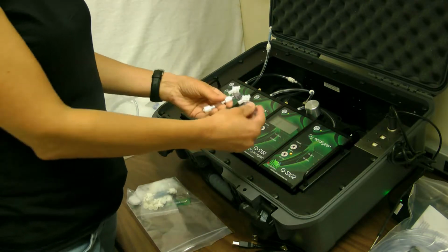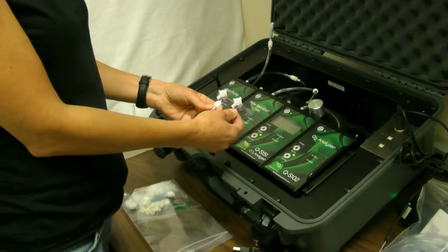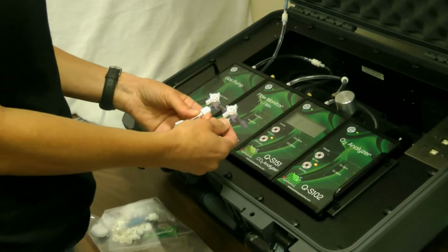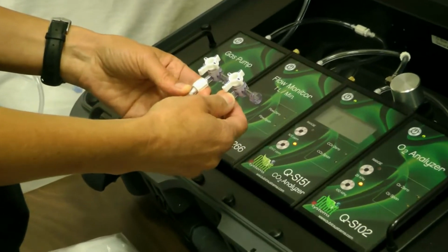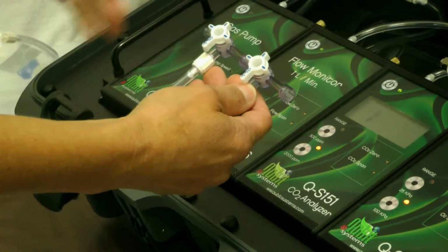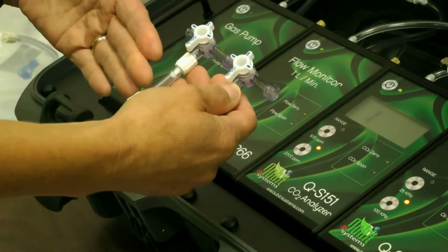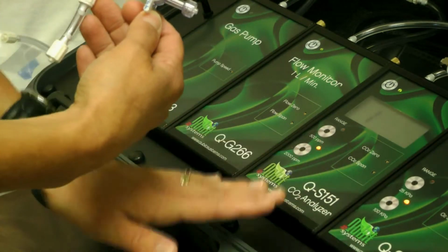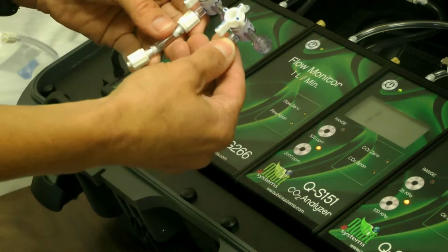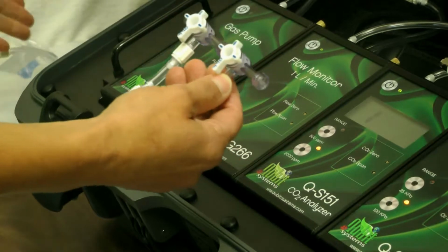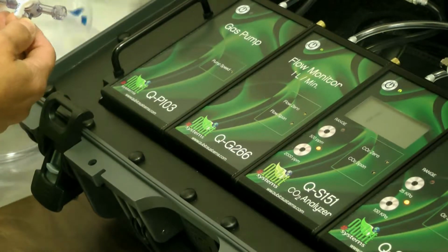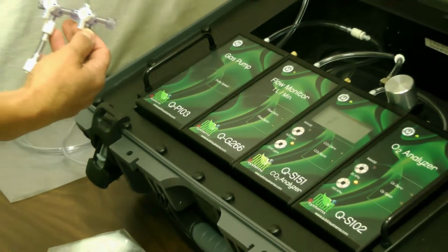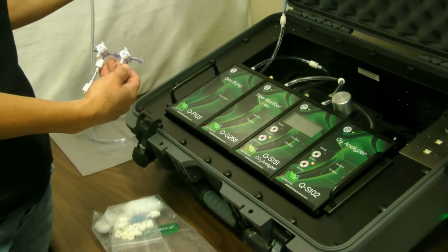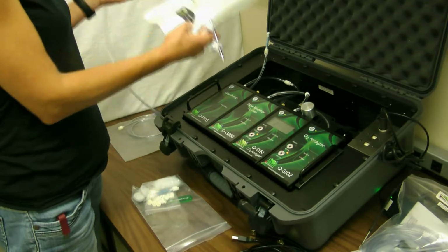We also provide manual valves to set up the system when you're doing your measurements of your sample, so you can easily switch between a reference mode and the analysis mode. There's only one set of analyzers, so in order to measure reference or background levels of CO2 and oxygen, you need to measure the gas that is coming from your gas source, which will be either air or CO2 scrubbed air that you can place inside a gas bag, which is also provided with the system.